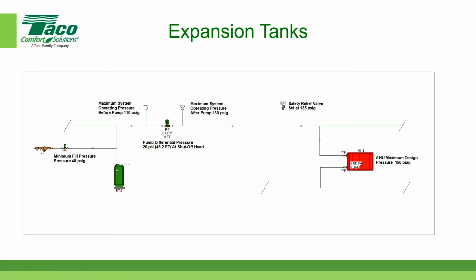There was a question. Where did you get the delta P for the pump? So in this case, I had selected a pump, and the differential pressure at shutoff head, in other words, I happened to pick a pump that had a shutoff head of approximately 20 pounds.